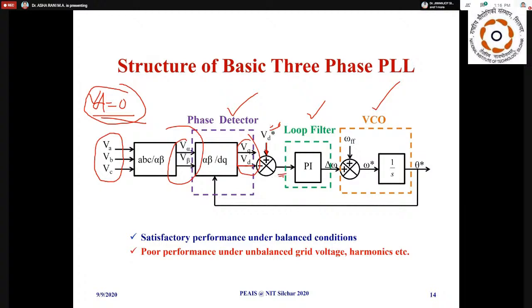So what the loop filter will do is minimize the frequency error of the loop. You can see that an additional component is getting added here, which is nothing but the feed forward omega. This generally corresponds to the 50 Hertz frequency of the grid. We know that the supply frequency of the grid is nothing but 50 Hertz, even though it is not always constant.